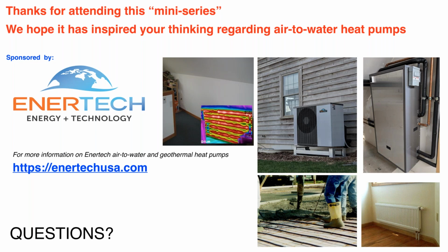Okay, the next question is defrost time. What is the average duration in defrost mode? Well, the answer is it depends. There's quite a lot of variation depending upon the amount of moisture in the air, the temperature, how long it's been running. So it typically is going to defrost for 5 to 10 minutes, but it could be less than 5 minutes. The max, if I remember right, is about 12 minutes.